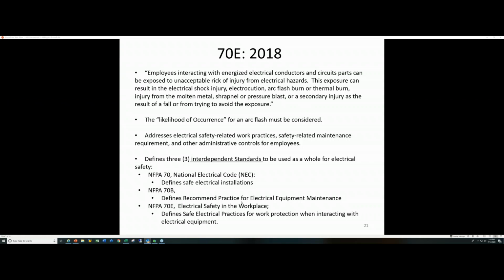Now, why is that important? Well, that's very important because if you are basing your design and your system off of coordination, you have to take into account that breakers that may be 50, 40, or 60 years old, and all these clearing devices, actually function in the 5 milliseconds they need to or less and provide the current limiting that they're designed to do. If you're not maintaining them, then all bets are off. You can do 100 studies and not maintain your equipment, and you're not doing yourself any justice.